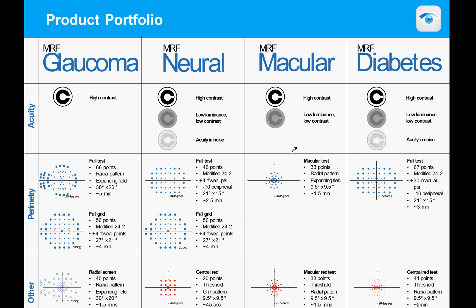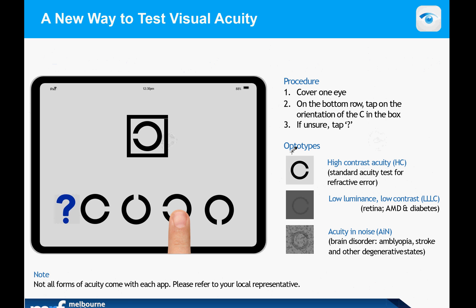There is also an acuity in noise version which is very sensitive for neural disease. Perimetry tests allow a 24-2 grid, a radial grid, or a specialized grid, with screening tests available for a glaucoma pattern. The acuity target is a Landolt C, which comes in one of four orientations. The patient selects the orientation of the C within a box. With children, we often say the wheel in the box is broken — show me which part is broken. High contrast, low luminance, low contrast, and acuity-in-noise versions are available for different applications.